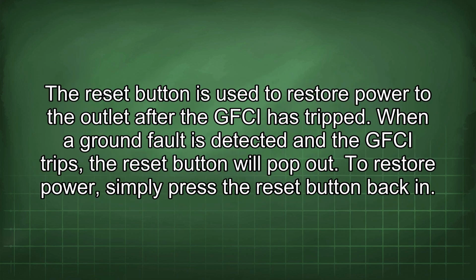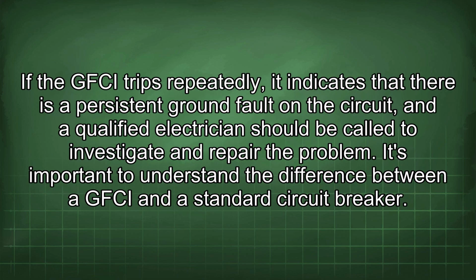The reset button is used to restore power to the outlet after the GFCI has tripped. When a ground fault is detected and the GFCI trips, the reset button will pop out. To restore power, simply press the reset button back in. If the GFCI trips repeatedly, it indicates that there is a persistent ground fault on the circuit, and a qualified electrician should be called to investigate and repair the problem.